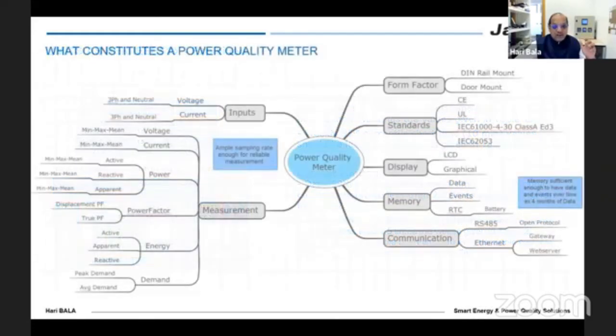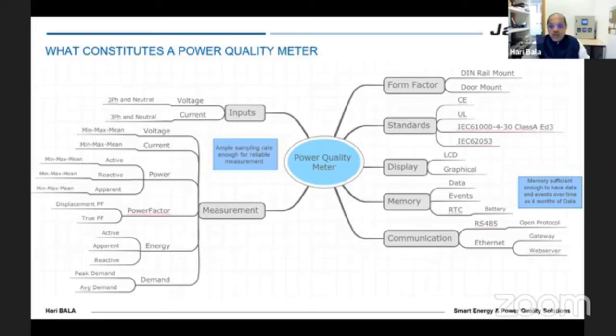That is where, when you choose our power quality meter, you should have a certain amount of information on how you want to do the measurement and what kind of specification it should have. The first one is, as Shrikant just talked about, UL: the product has to be UL certified. 61000-4-30 is a standard which needs to be type tested for. That is a requirement for a power quality meter. And then, of course, there are other standards like 62053 and CE, which are the normal safety regulations.